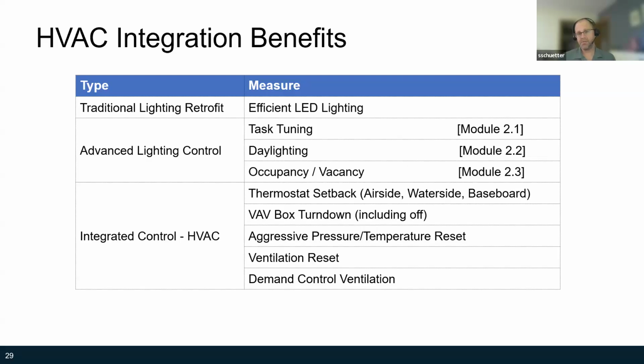Thermostat setbacks are the most utilized strategy for HVAC systems. When the occupancy signals from the lighting system indicate an unoccupied status during the day, the active heating and cooling set points are set back by typically a few degrees. In the case of a variable air volume system, additional strategies can be incorporated, such as in ASHRAE Guideline 36, to control the airflow.